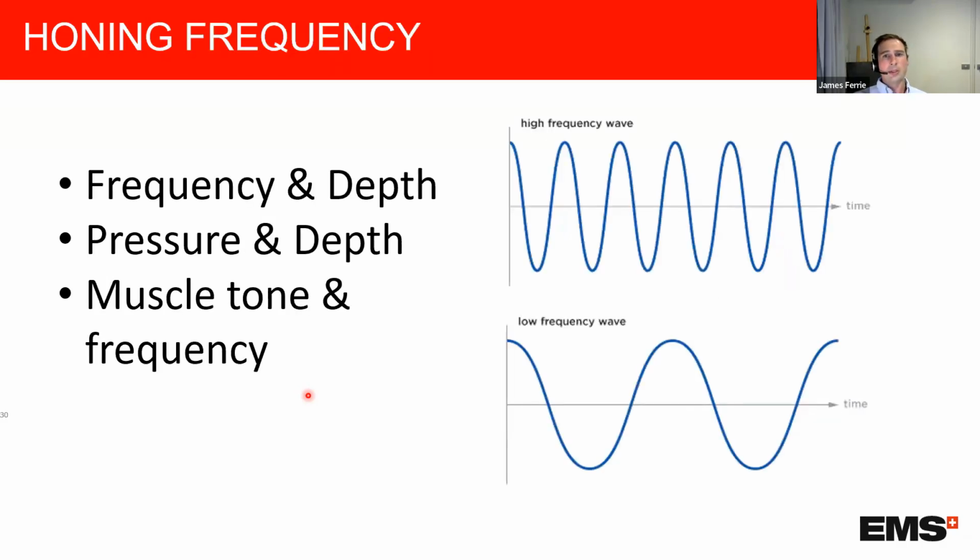As I said, there's a bit of a relationship when it comes to ultrasound, and it's similar with shockwave as well, that a higher frequency can lose a little bit of punch in terms of depth. When we're treating really superficial things, this doesn't matter. When we're treating deeper indications, when we want all the depth penetration that we can, that's where it's more important to lower that frequency and maybe use 8 to 10 hertz.